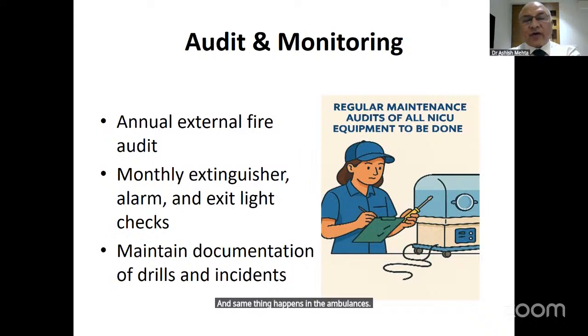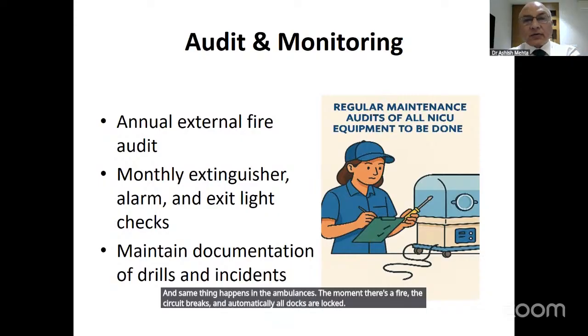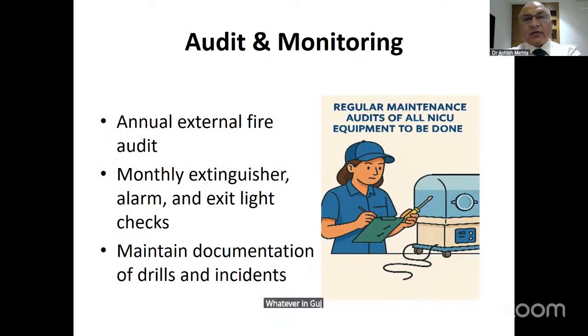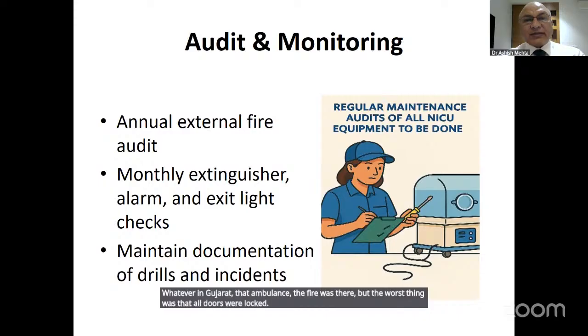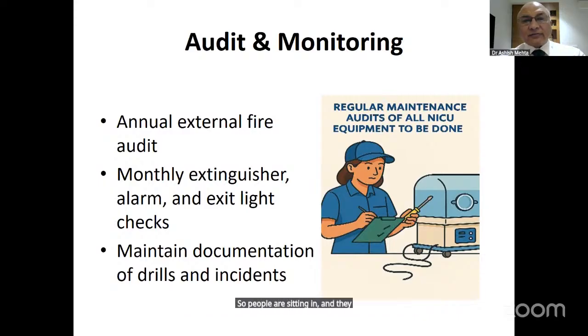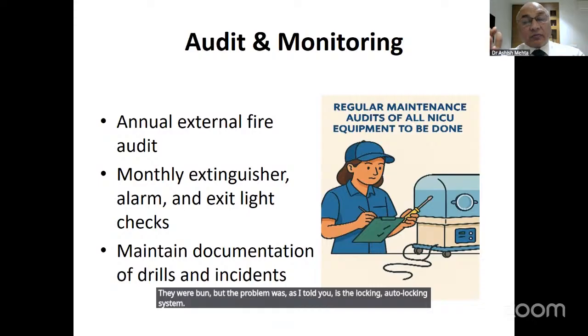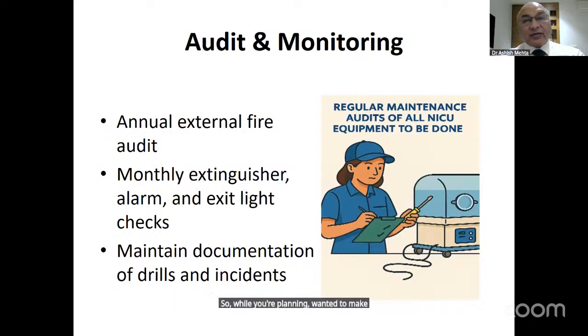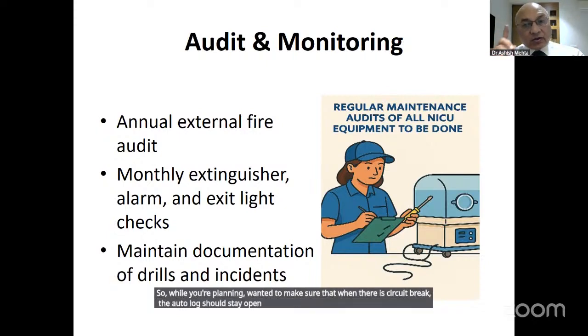The moment there's a fire, the circuit breaks and automatically all doors lock. That's what happened in Gujarat - the ambulance caught fire, but the worst thing was that all doors were locked, so people sitting inside were burned. The problem was, as I told you, the auto-locking system. So while planning, one needs to make sure that when there is a circuit break, the auto-lock should stay open, not closed. That's the most important part of the planning.